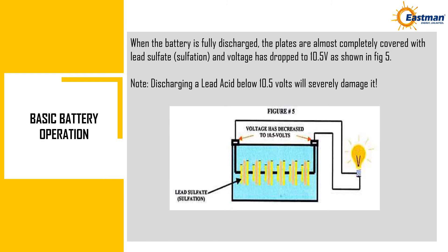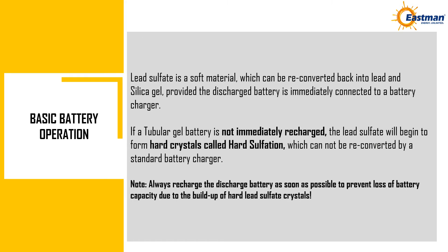Note that discharging a lead acid battery below 10.5 volts will severely damage it. Lead sulfate is a soft material which can be reconverted back into lead, provided the discharged battery is immediately connected to a battery charger. If a tubular gel battery is not immediately recharged, the lead sulfate will begin to form hard crystals called hard sulfation, which cannot be reconverted by a standard battery charger. Always recharge a discharged battery as soon as possible to prevent loss of battery capacity due to the buildup of hard lead sulfate crystals.